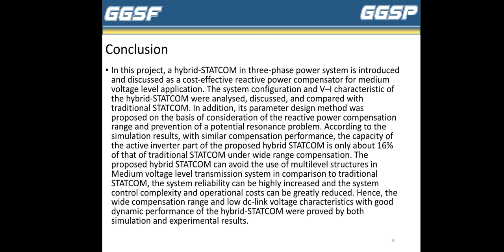With similar compensation performance, the capacity of the active inverter part of the proposed hybrid STATCOM is only about 16% of that of the traditional STATCOM under wide range compensation. The proposed hybrid STATCOM can avoid the use of a multi-level structure in medium voltage level transmission systems. In comparison to the traditional STATCOM, the system reliability can be highly increased and the system control complexity and operational cost can be greatly reduced. Hence, the wide compensation range and low DC link voltage characteristics with good dynamic performance of the hybrid STATCOM were proved by both simulation and experimental results. Next is the reference.